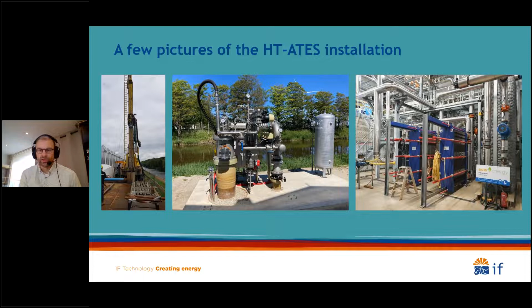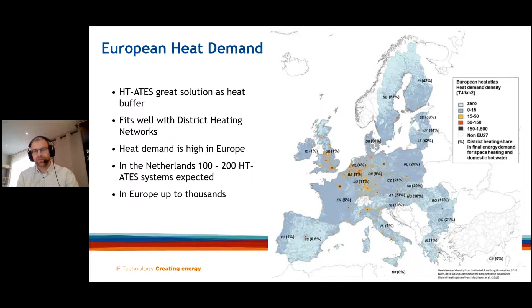Now, what do we expect for the next period? We think high temperature ATES is a great solution as a heat buffer, because you can store at high temperatures which can be directly used by greenhouses or residential areas. That fits very well with district heating systems - I'm not sure if it will be 4th or 5th generation heat networks, but I think it will be 4th. Heat demand in Europe is high, and in the Netherlands it's expected that about 100 to 200 high temperature storage systems could be realized, especially in combination with deep geothermal wells and other industrial heat sources. Other calculations count up to 2,000 high temperature storage systems in Europe.